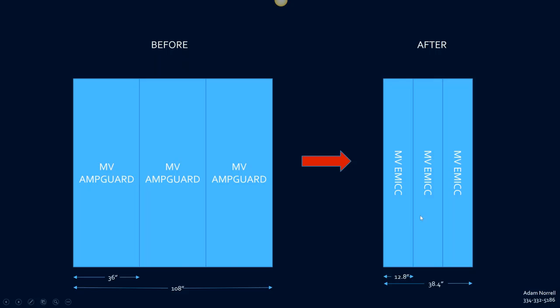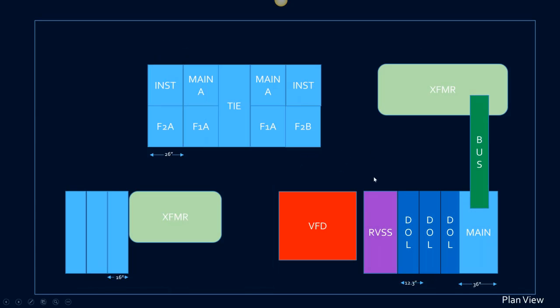And if we take another look at it and get a little bit creative and talk to the folks at EMIC, now we're down to 12.8 inches per starter. And that still includes our protective relay of our choice, and contactor and fuses, and a non-load break disconnect switch. So what have we done to our room? We have significantly reduced our footprint over here in our medium voltage motor control.